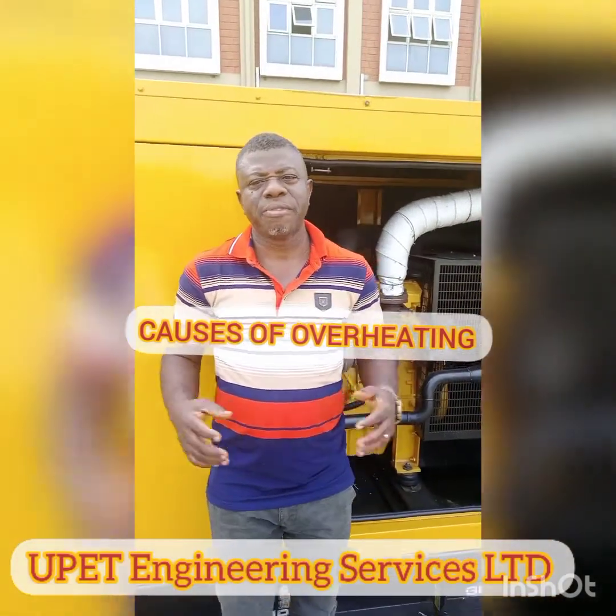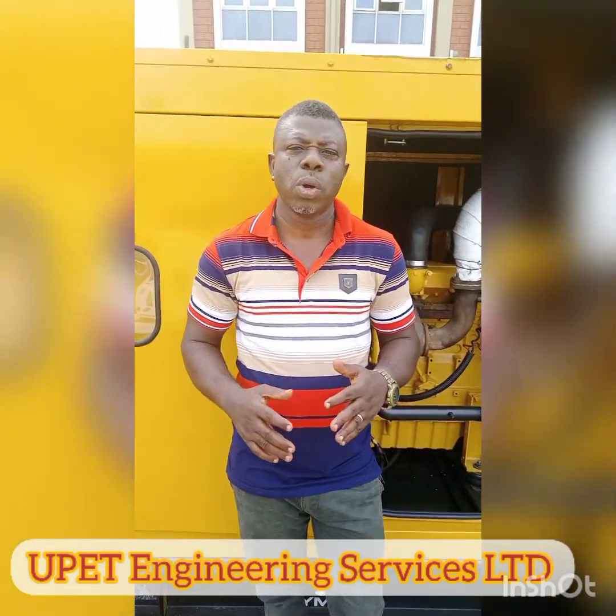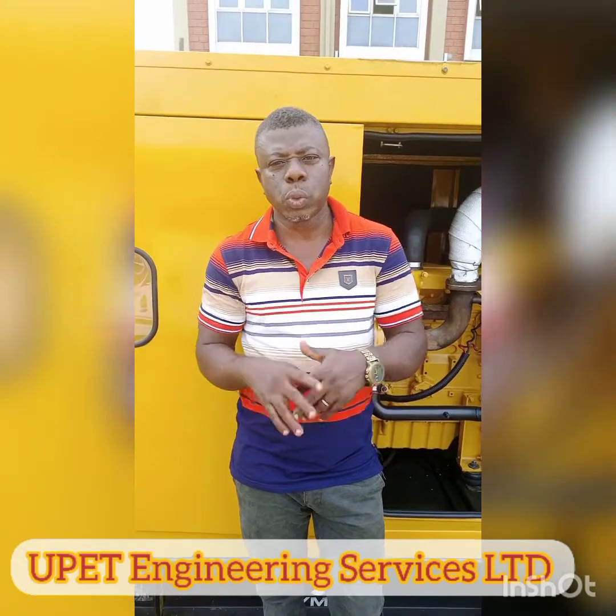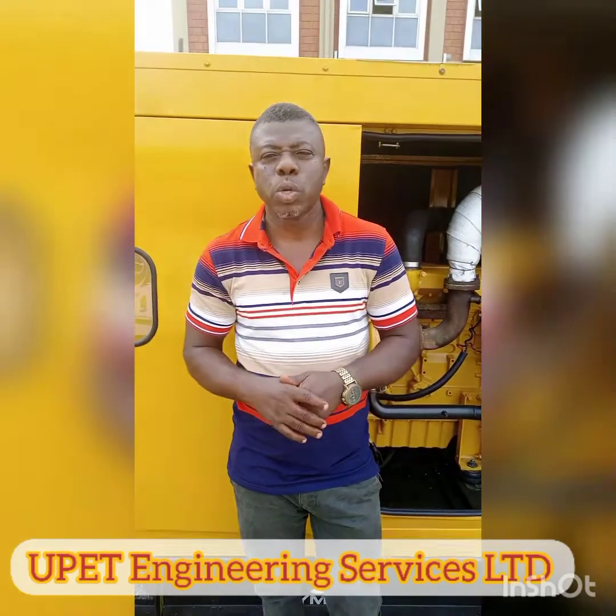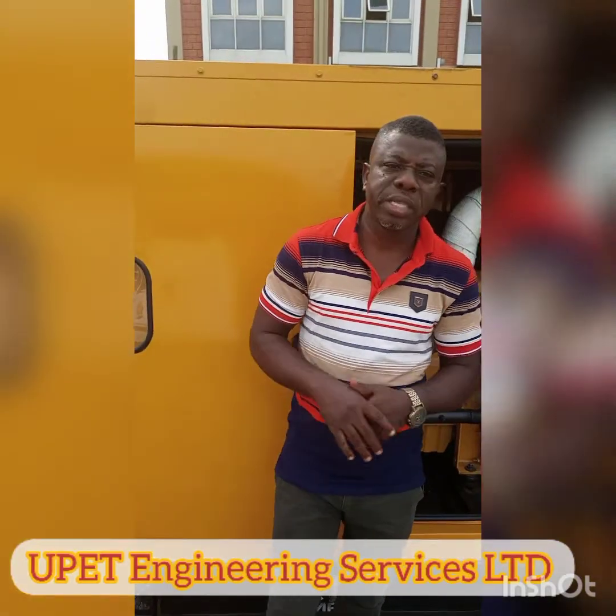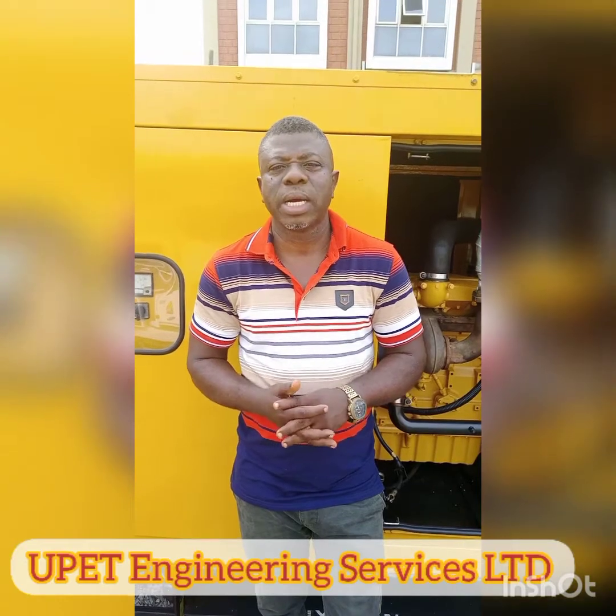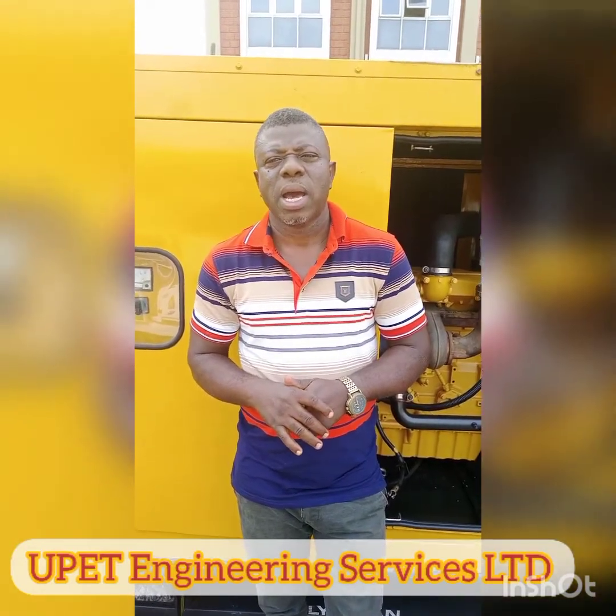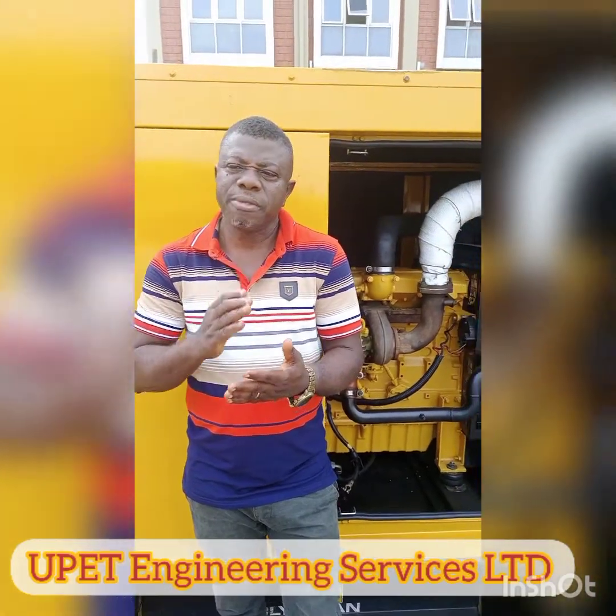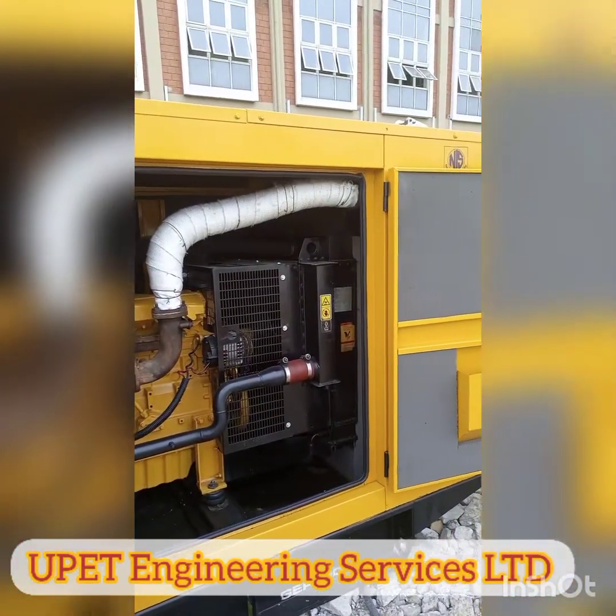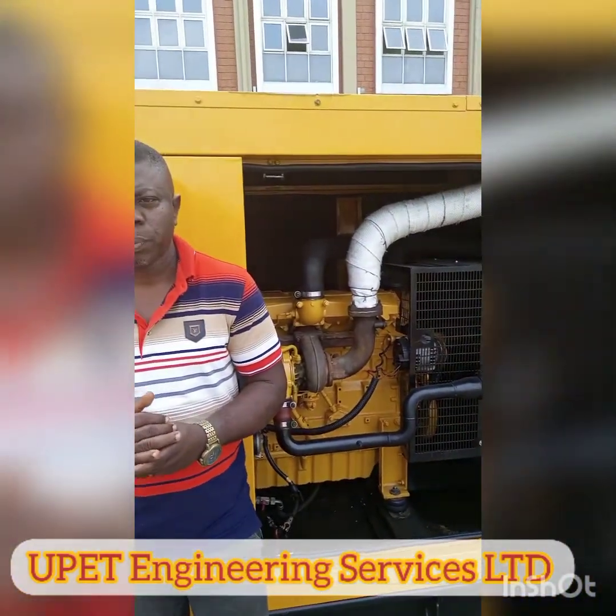Today I want to take you through the causes of overheating in diesel gensets. There are many factors that can lead to that, which I want you to be aware of, so that anytime you are having challenges, you can check one, two, or three things before you call your vendor or your engineer to come and sort it out. So number one, when the diesel genset is overheating, first of all check if the fan belt is there, check if the radiator is not dirty, and also check if the fan belt is properly tensioned. Okay, let me go into details.